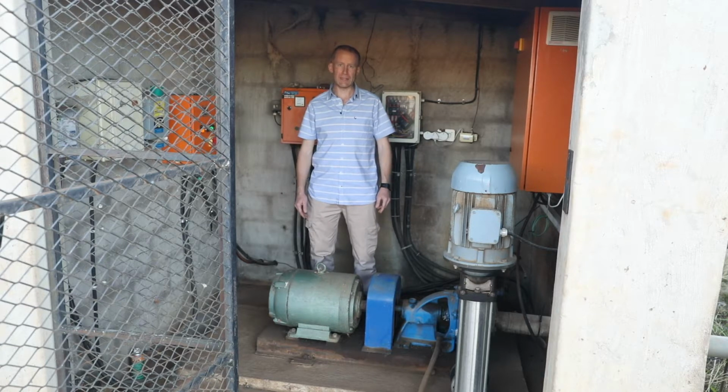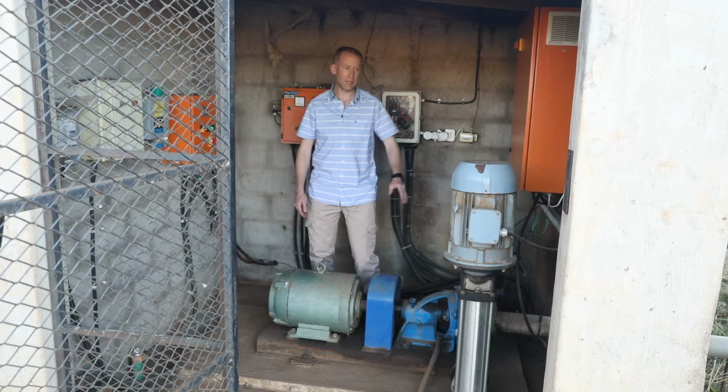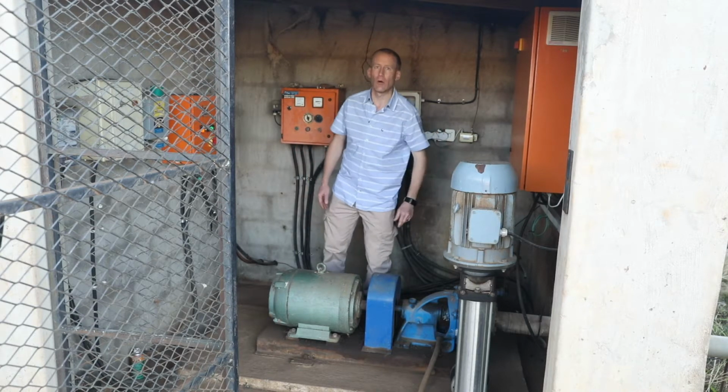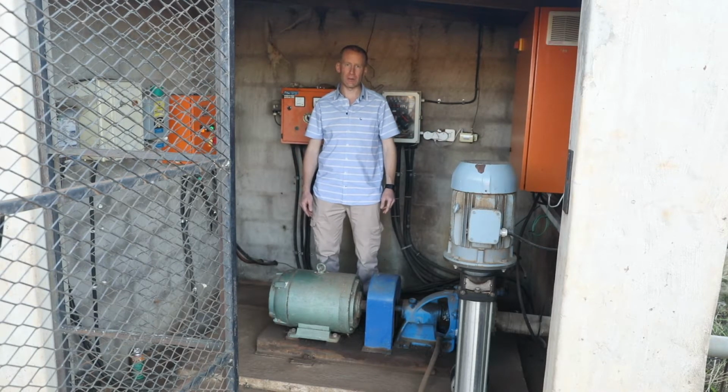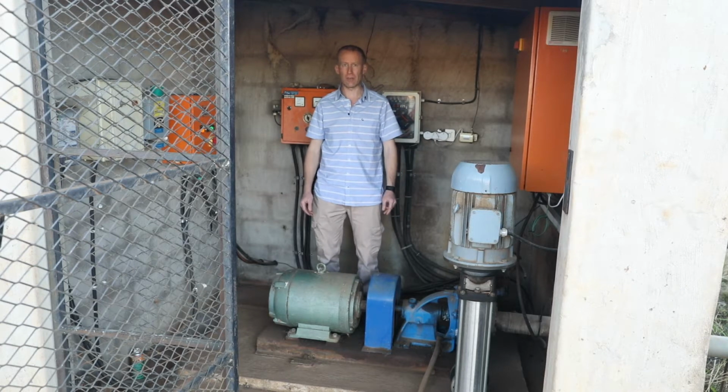After analyzing the data, we determined that the best pump and motor for the flow rate would be this unit over here, which runs off a 9 kilowatt motor. That's a reduction from a 30 kilowatt motor drawing 22 kilowatts down to a 9 kilowatt motor. When we are running the 9 kilowatt motor with the pivot optimizer and a variable speed drive, the system draws an average of 5 kilowatts. This is a reduction from 22 kilowatts, or a saving of 75%.